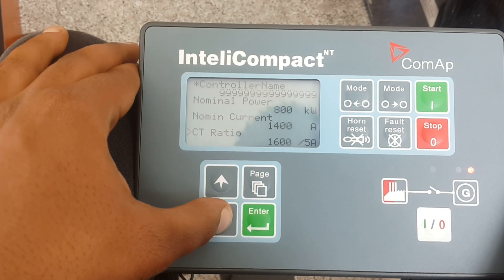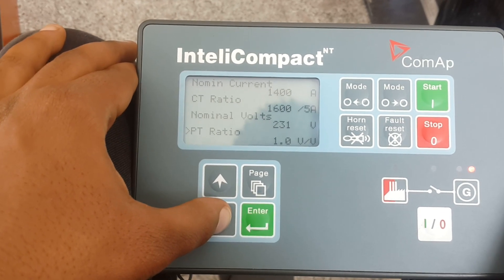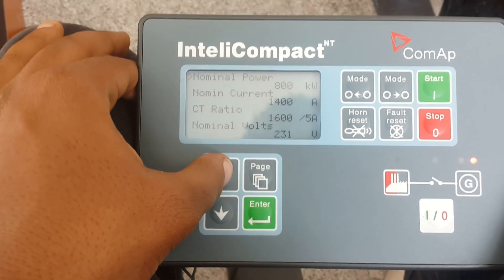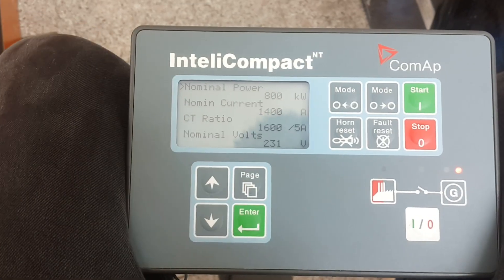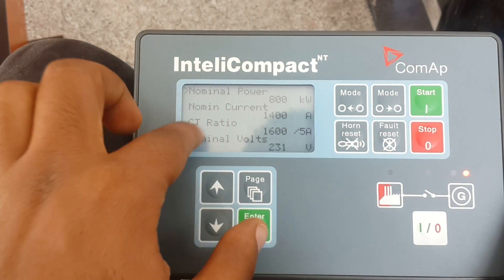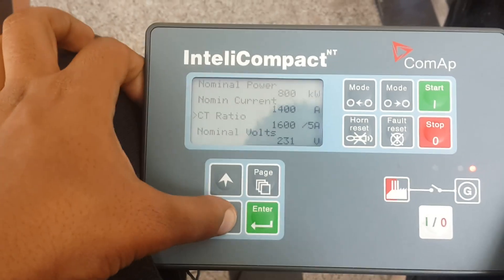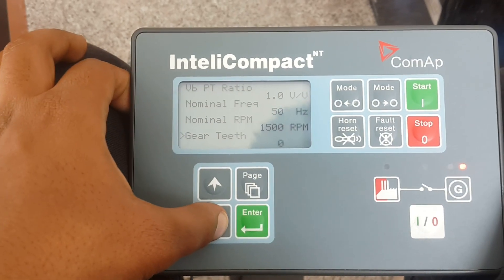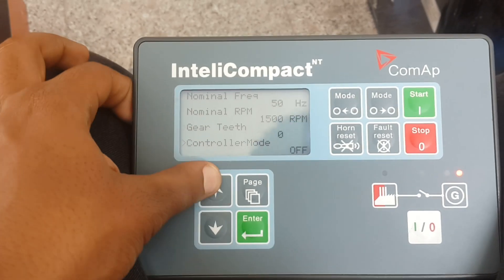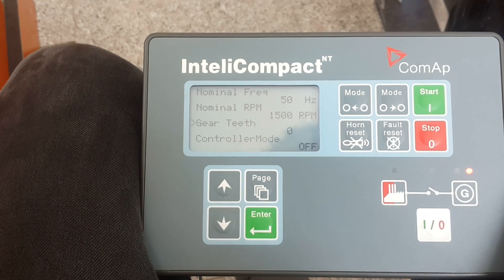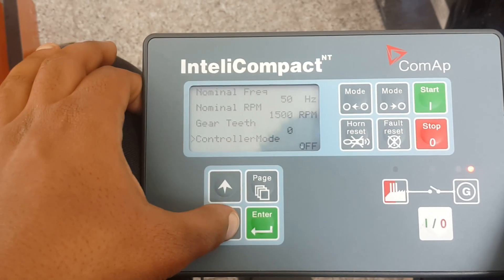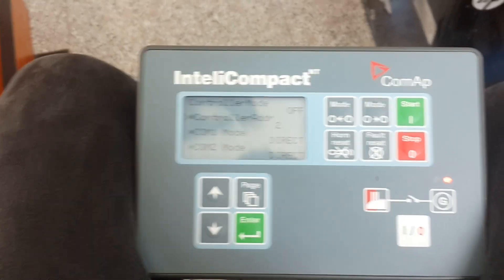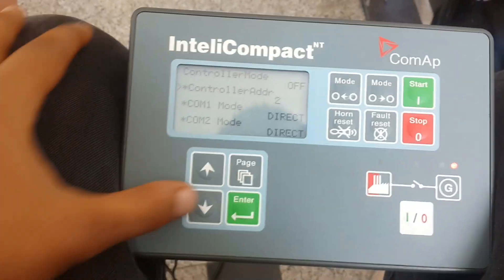Nominal power, current CT ratio, nominal voltage, PT ratio — these things are really necessary to make the syncing. The CT should be from your gen set side, and the ratio and everything is here. The nominal frequency, nominal RPM — most of the time you keep the gear teeth on zero if you don't want to use the magnetic pickup input. The controller mode is in off mode, and then you have to give it an address so the controller knows which one is the master and which is the slave.